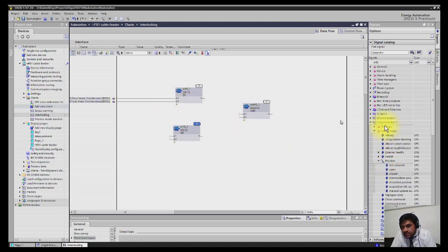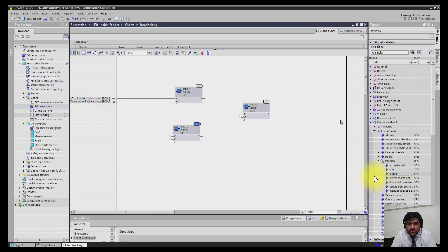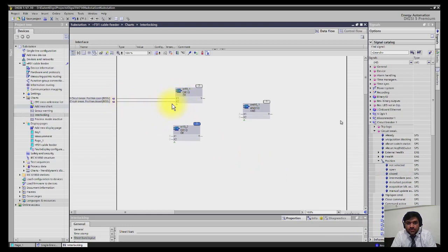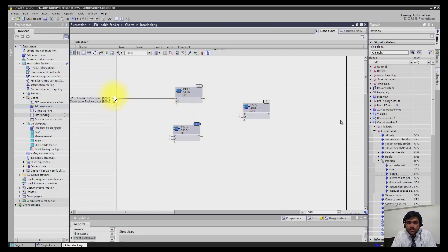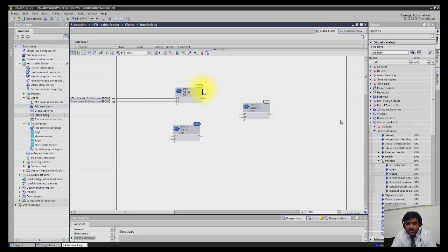Now I will select the inputs. For the breaker, I will select open position, drag and drop here, and then close position, drag and drop here, and connect to X1 and X2. If breaker is open it will be one, and output will be connected here. If breaker is closed it will be one here. If breaker is neither open nor closed, there will be zero and the breaker output is not one, so you can't operate the breaker. This is how you are building the logics in the charts.